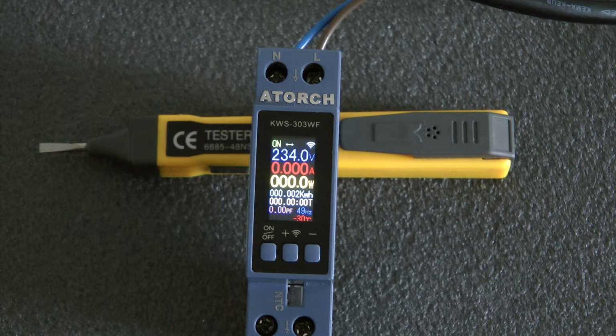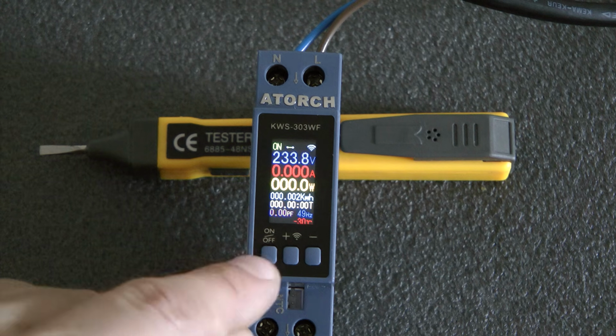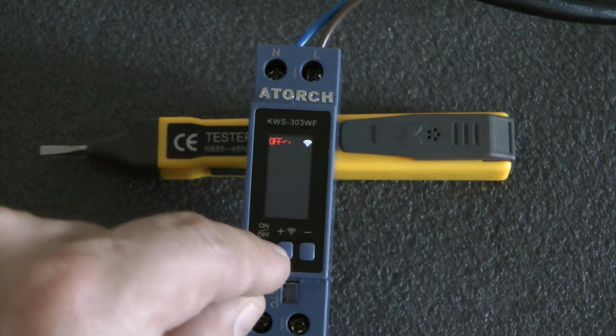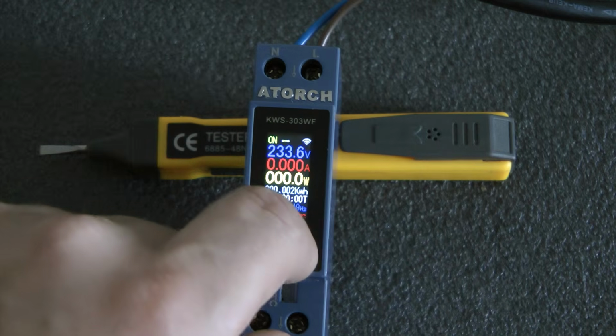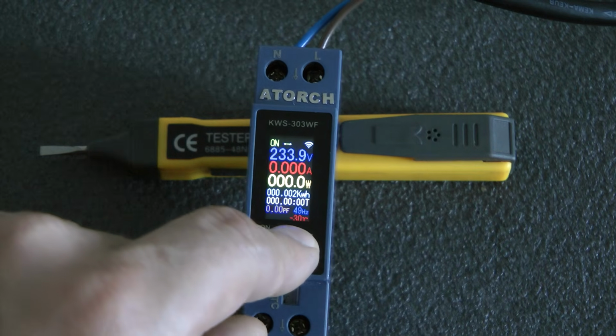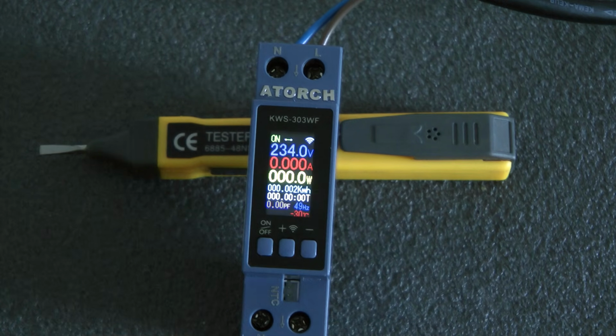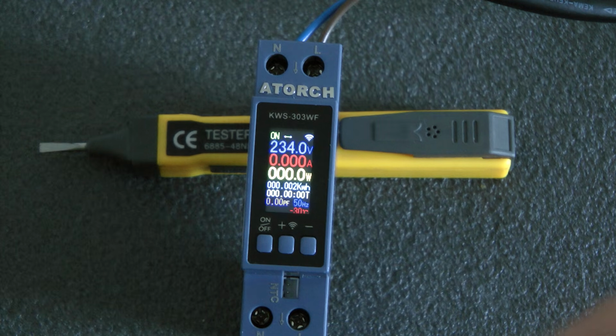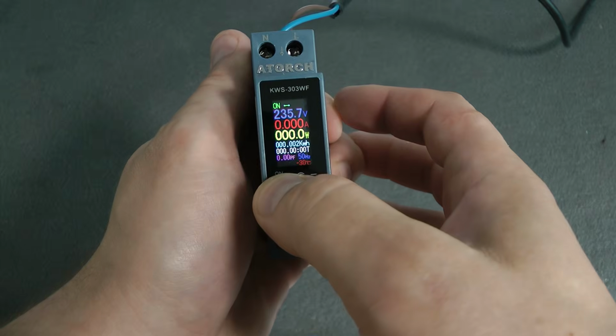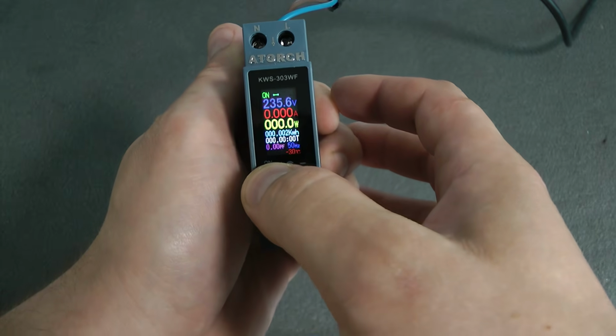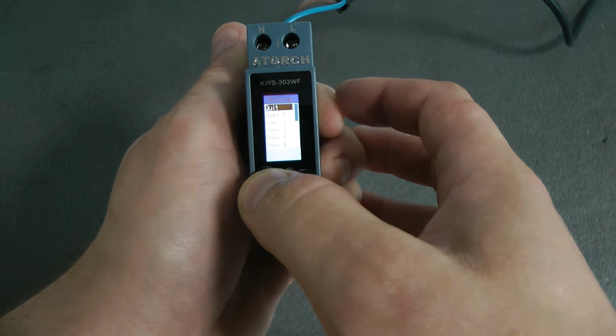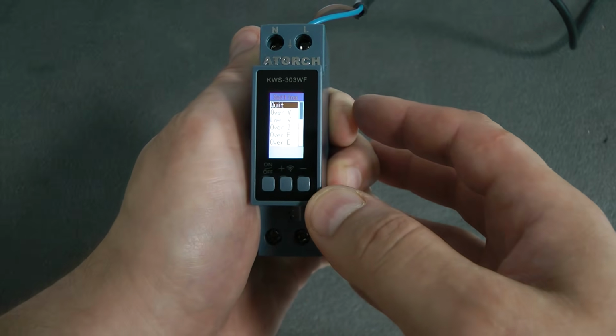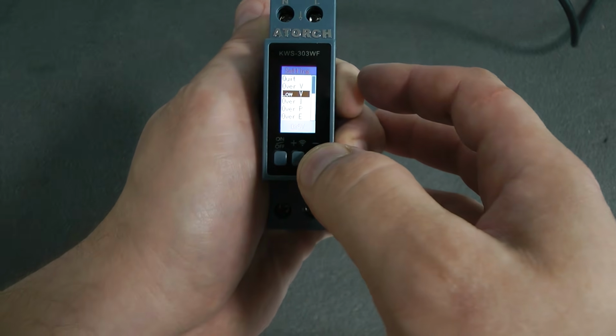There are 3 buttons under the screen. The left one manually turns the load on and off, and the other 2 are needed for navigating through the menu and changing parameters. With them, you can set the protection thresholds directly on the relay, without Tuya and even without the internet. Hold the relay on/off button for more than 5 seconds, and you enter the relay parameter settings menu. The plus and minus buttons are used to navigate through the menu.